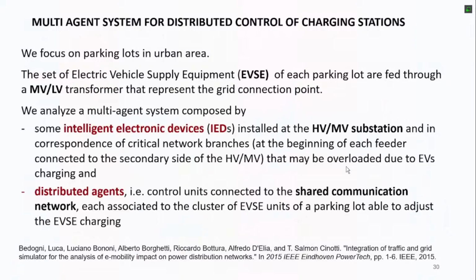We analyze a multi-agent system composed of intelligent electronic devices, special protection installed in the high voltage/medium voltage substation and at critical network branches at the beginning of each feeder connected to the secondary side of the substation, for example, branches that may be overloaded due to electric vehicle charging. There are also distributed agents: control units in the parking lot connected to the shared communication network, each associated with a cluster of charging units in the parking lot.